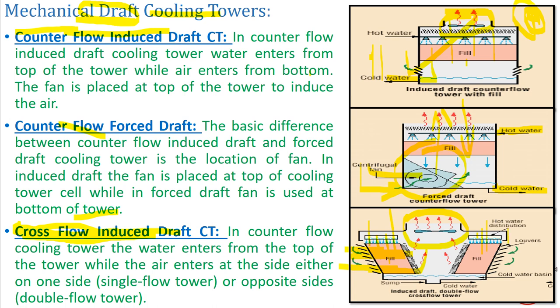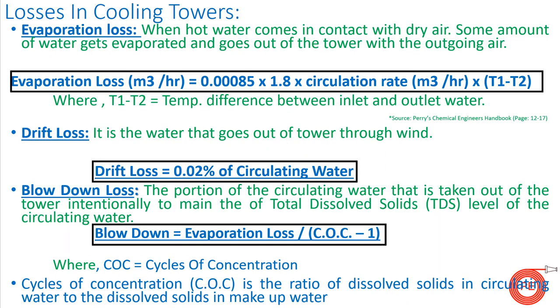In a cross flow cooling tower, the hot water distribution is on the sides of the tower, not centrally. Louvers facilitate the movement of air inside. Hot water comes from the top and cold water exits from the bottom. Cross flow towers can be double flow — where air enters from both sides — or single flow, where air enters from only one side.